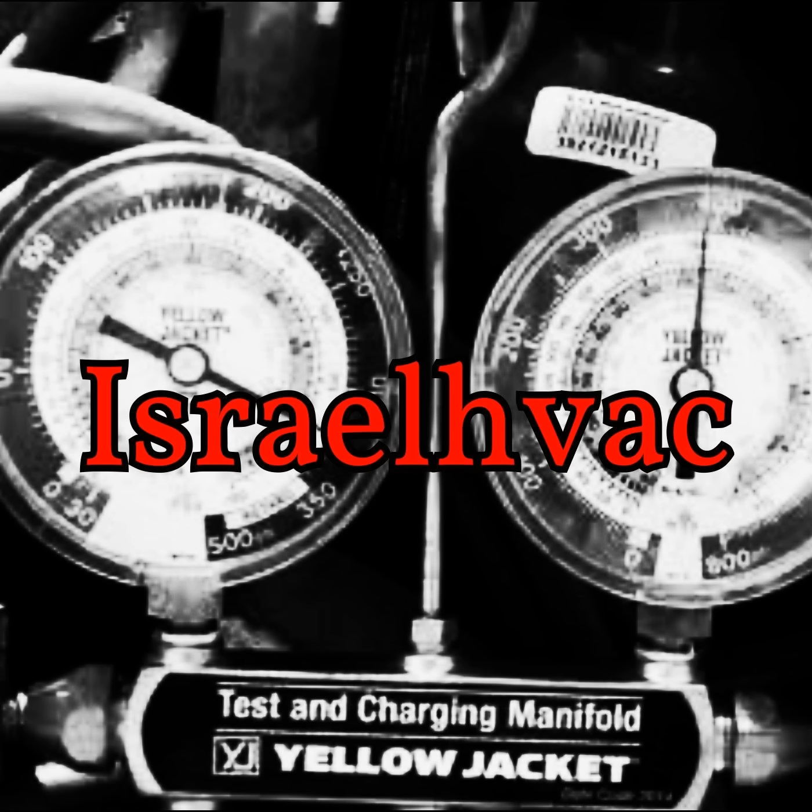It's got a good contactor, a good capacitor, a Mars 440 capacitor in it. It's got a good condenser fan motor and a Copeland scroll compressor. So the only downside to that unit is the microchannel coil. Yep, exactly, because I've got about a handful of them out there.